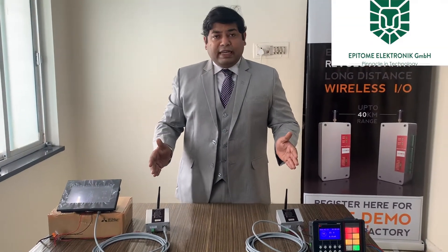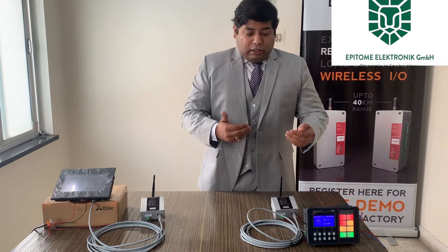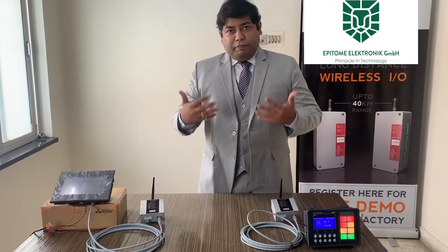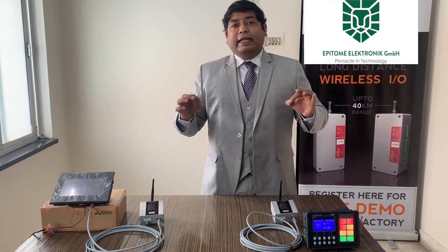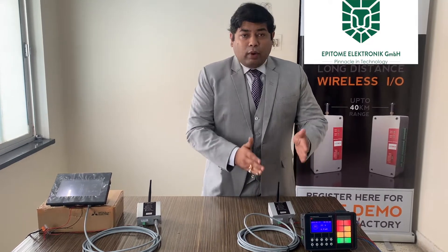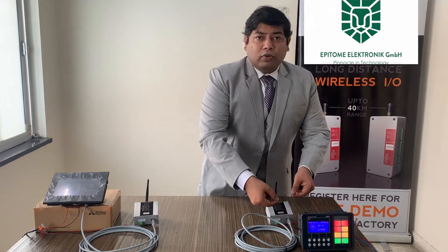The speed of this device can be from 1 millisecond to 30 milliseconds, and being a free protocol communicating TCP/IP, it can communicate with all kinds of PLCs — it can be Siemens, Schneider, Allen Bradley — all the different brands can communicate via this device, as it is a transparent device.